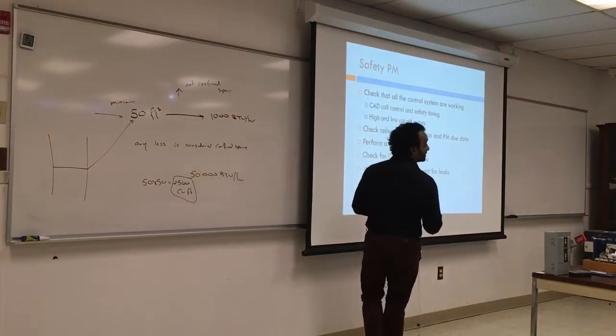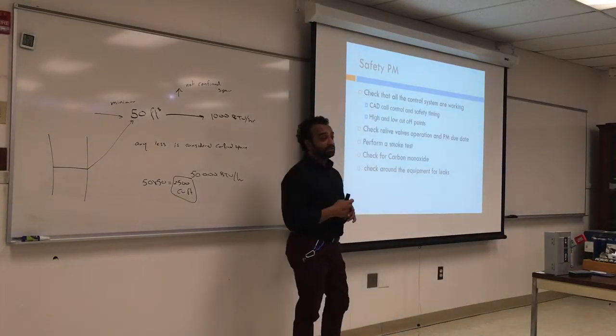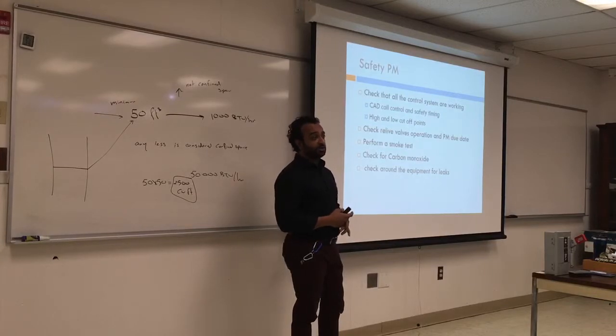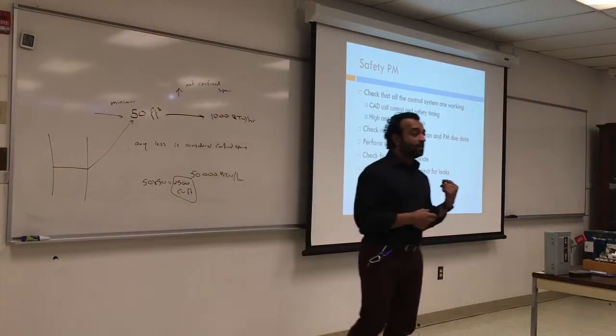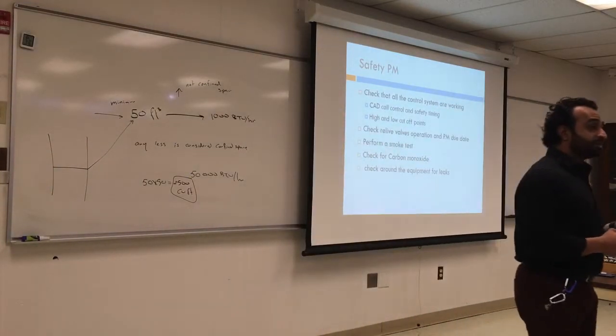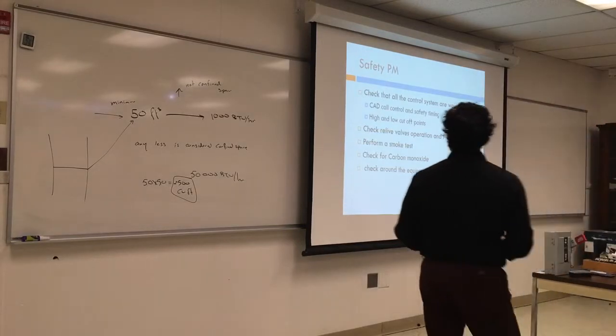High and low cutoff points. Steam is very critical. Make sure you wait for the steam to start rising and to build pressure. Once it reaches 2 psi, it should cut off. Otherwise, something is wrong with the pressure cutoff. And if it's faulty, you will have to change it.